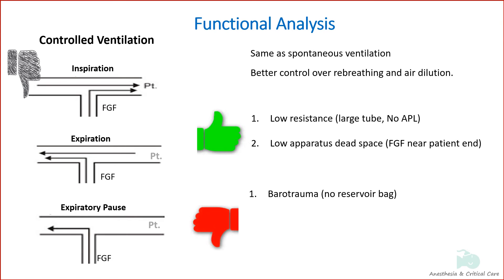However, there is significant risk of barotrauma and since there is no reservoir bag the pressure reduction effect is not there. The operator doesn't feel the bag during ventilation. It is also difficult to scavenge the waste gas.